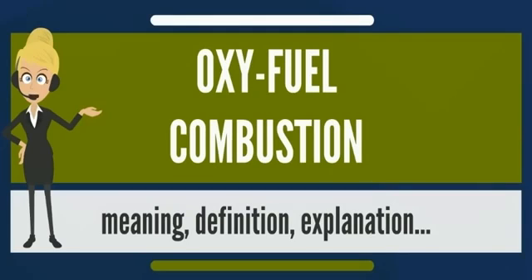Almost all of the nitrogen is removed from input air, yielding a stream that is approximately 95% oxygen. Firing with pure oxygen would result in too high a flame temperature, so the mixture is diluted by mixing with recycled flue gas or staged combustion. The recycled flue gas can also be used to carry fuel into the boiler and ensure adequate convective heat transfer to all boiler areas.